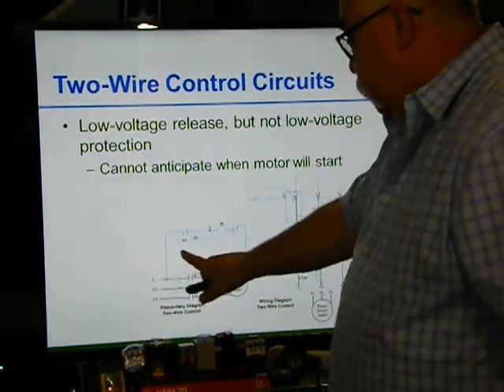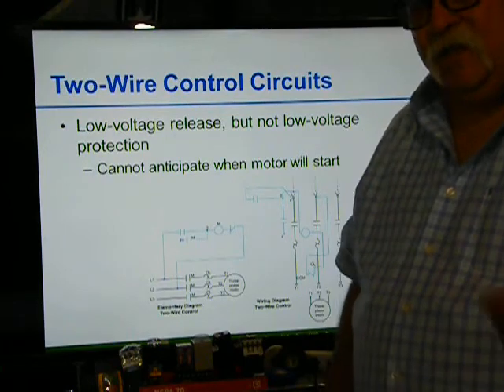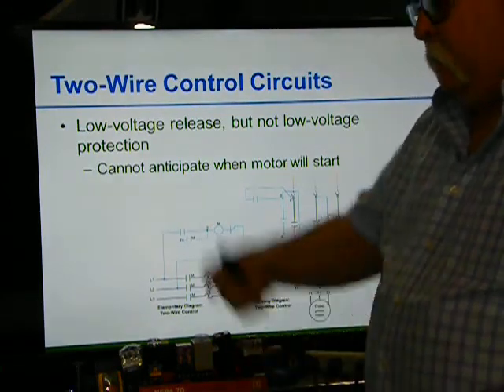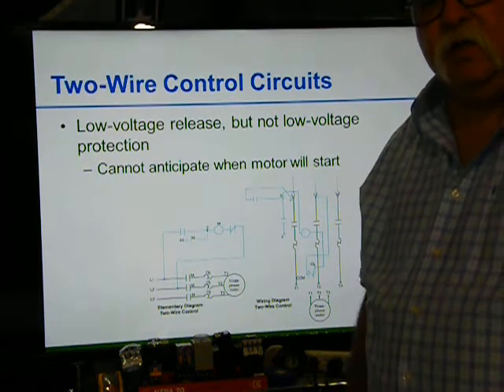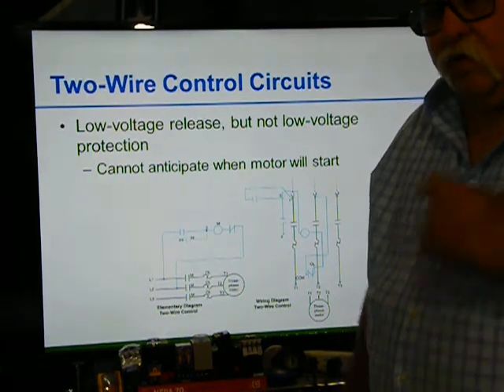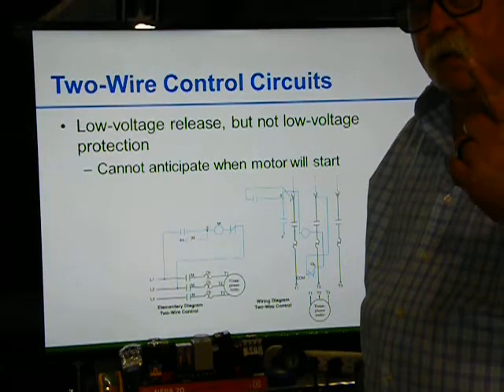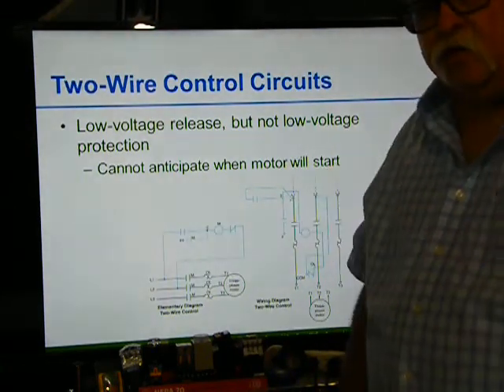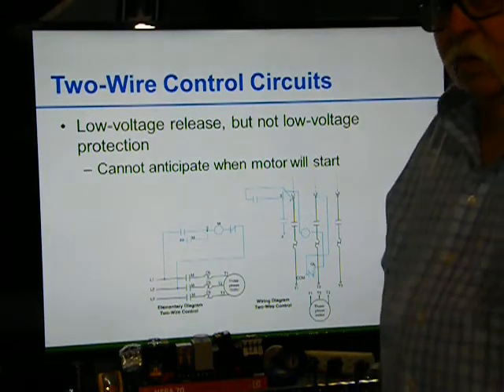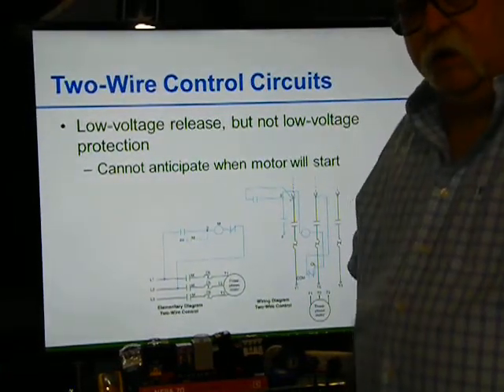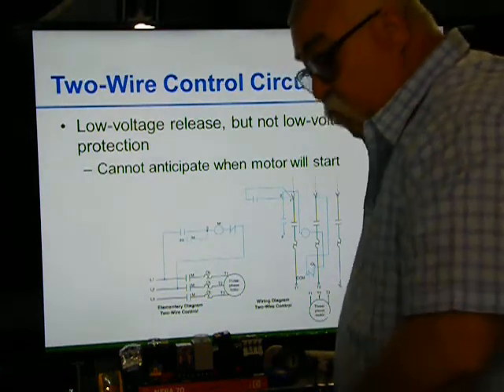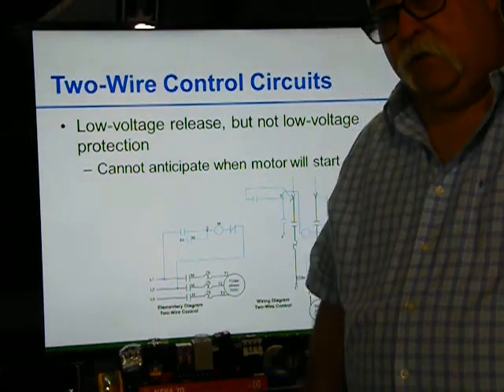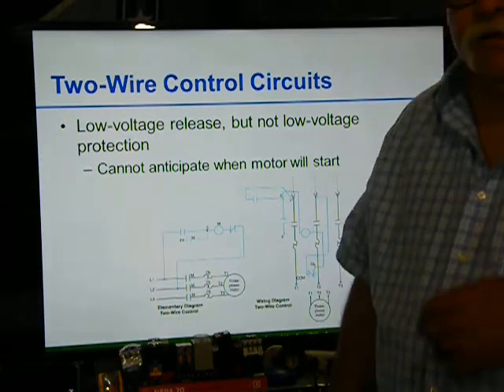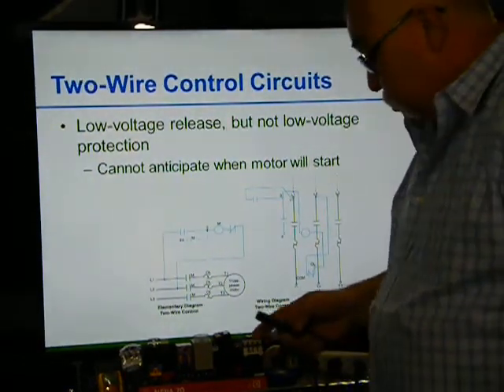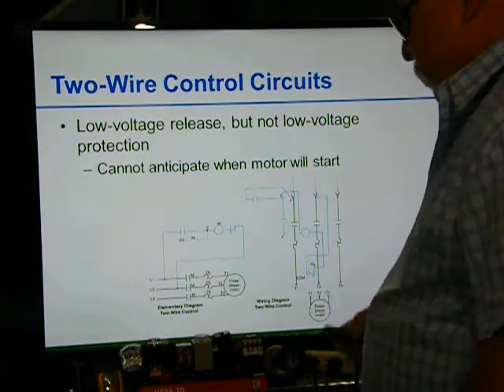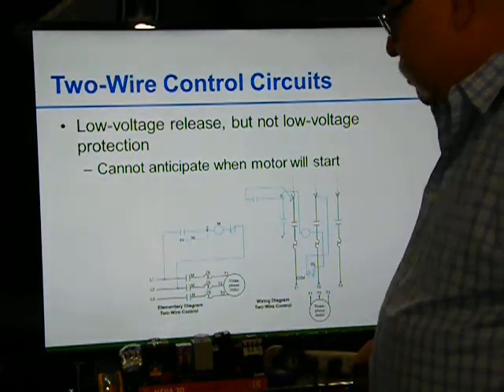I mean, you could come across over here and put one in a remote location, but that's the last thing you want with one of these. You turn this one off, somebody walks over there and turns that one on, and you don't even know it's there. So always, when you've got a two-wire connection, don't put more than one remote device to turn it on and off. Don't try to put any somewhere else, because if you turn the motor off going to work, and there's a switch somewhere else that you don't know about, that could turn it back on. Somebody else could turn it on you. There's things you can do, but I wouldn't advise it.